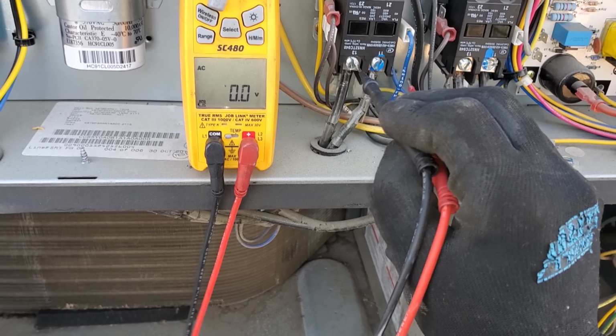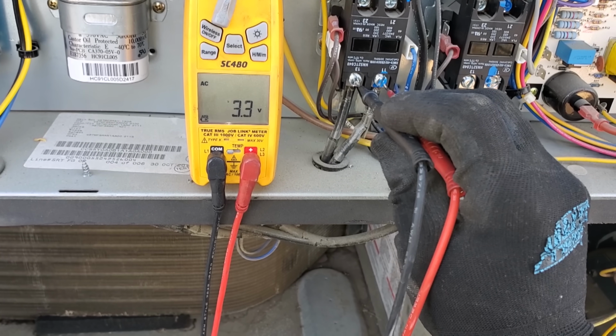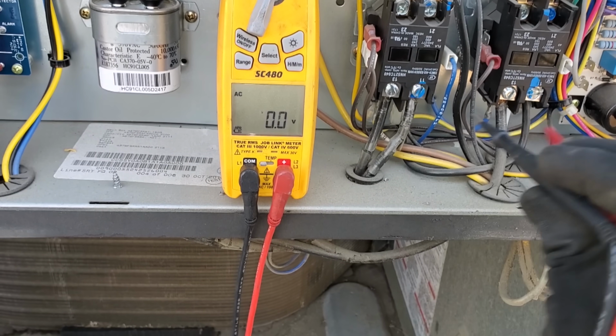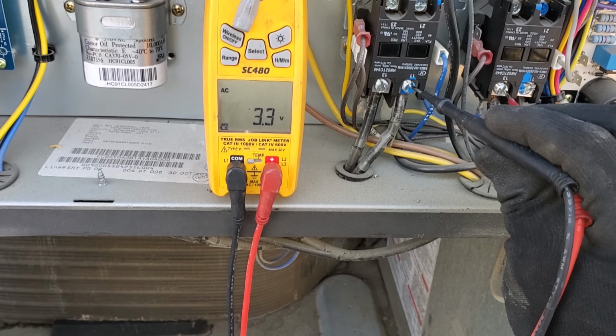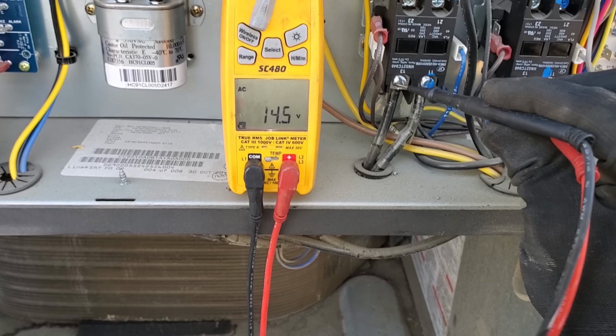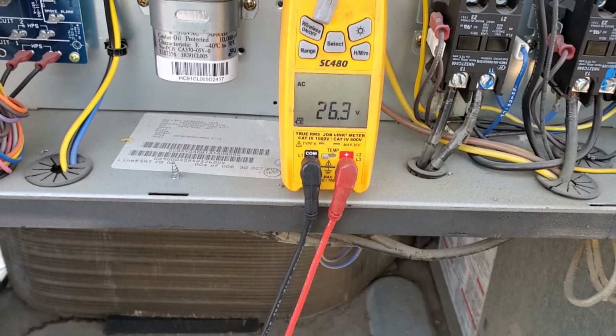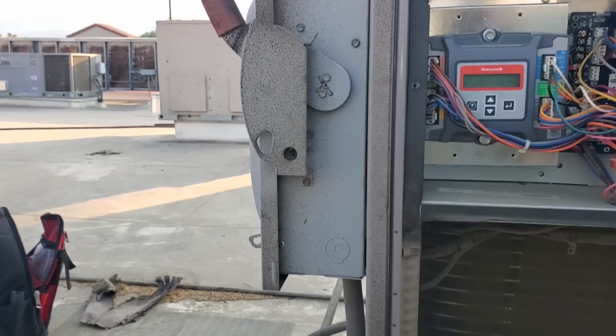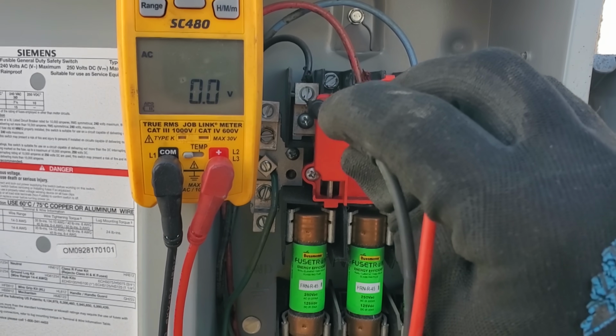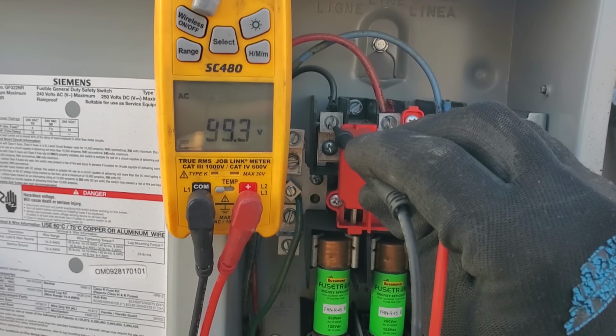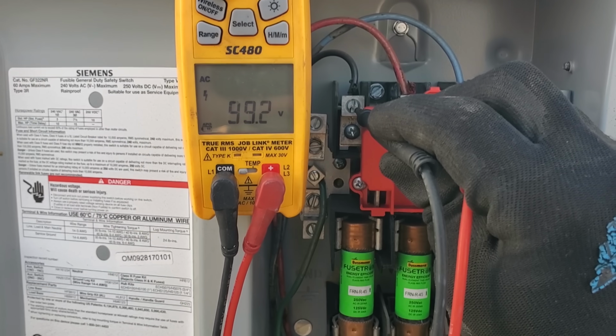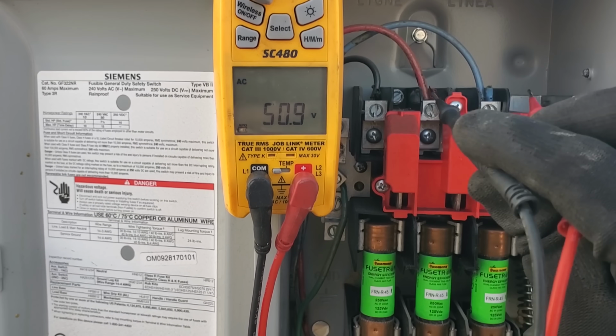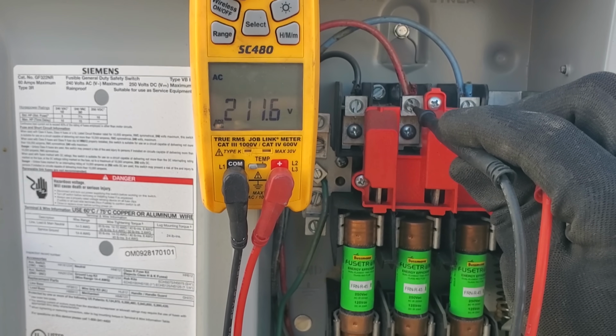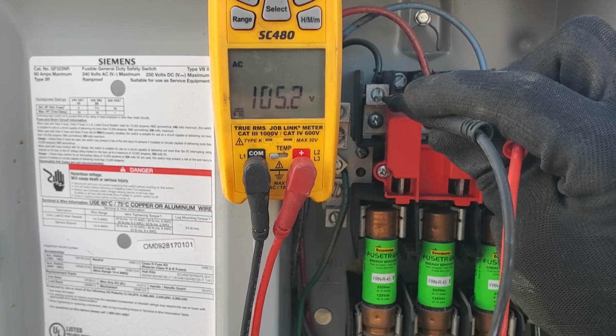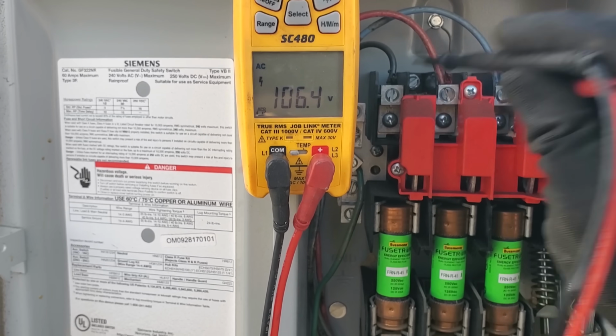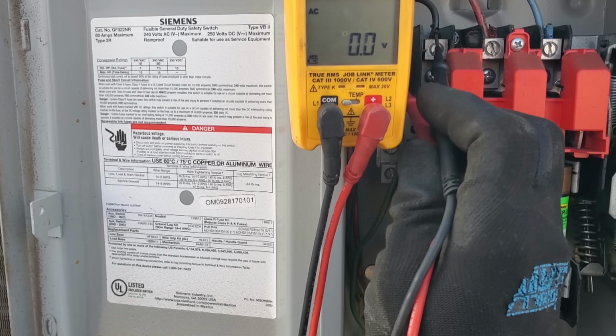All right, let's go ahead and check voltage. Looks like nothing. Something. So we're probably gonna have a blown fuse. Let's go and open up this disconnect switch. Let's see what we got going on in here. So this is incoming power. Boy, this is a 208 volt system, 3-phase. So 99, 1 to 2, 211, 2 to 3, and 1 to 3, 106. What the heck? All right, let's check to ground.